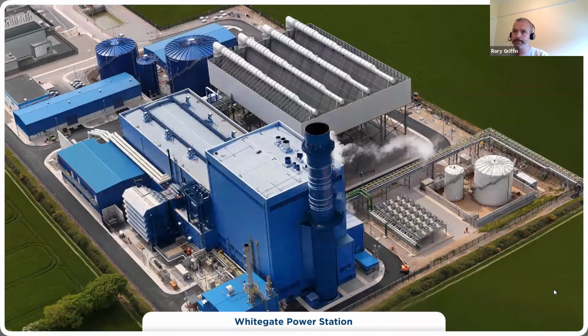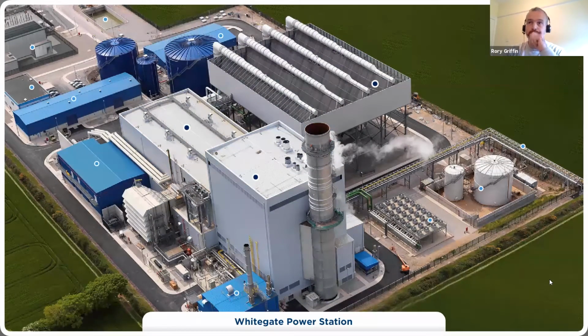So I'll just move on now to the actual site overview itself. I'll start up in the top corner here and give you a feel for what's what. As mentioned, we can take in up to 10 tons per hour of raw water from the local supply from Irish Water. This is drinking water, but it's not clean enough for the machine. So we pass the raw water through the treatment plant, where there's filtration. We add various chemicals to it and we come out with pure H2O. Once the H2O is created, it's stored here in the demineralized tank. This is then what's used to supply the machine.